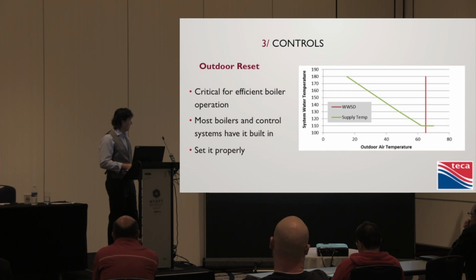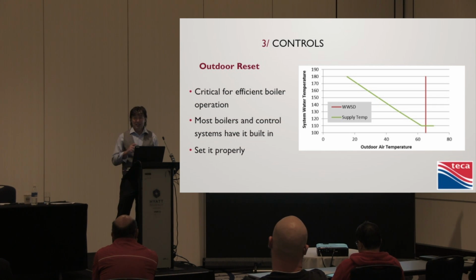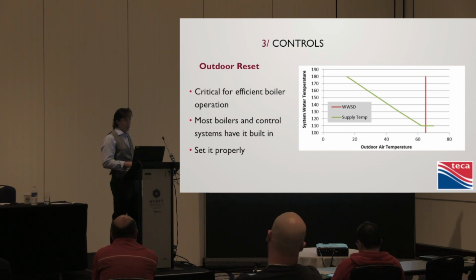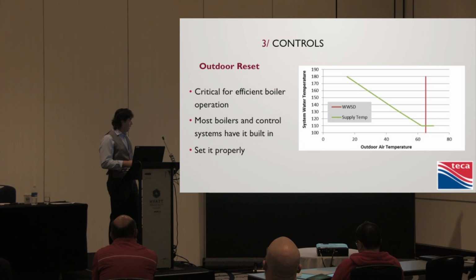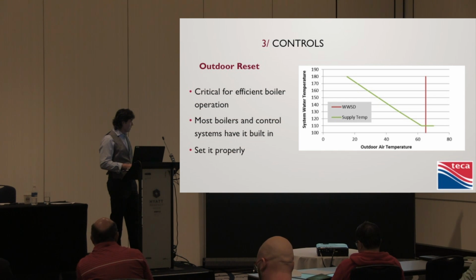We have to say that at 70 degrees, if my design water temperature at the worst case scenario is 180 degrees, then that means if my design temperature outdoors is, let's say, 0, coldest day is 0, at 0, I want you to be at 180. So compared to my minimum supply temperature, if I set my minimum supply, I can't heat with less than this. This would be more for baseboards, from 110 to 180. But still, there's huge savings to be had. Number one, when it gets to be 70 or 68 or whatever, tell the boiler to just shut off. How about that? And then when it's enabled because the outdoor temperature has dropped to this temperature, and as the temperature drops, tell the boiler to slowly increase the temperature of the supply water. The cooler that supply water temperature is, the more efficiently everything operates.